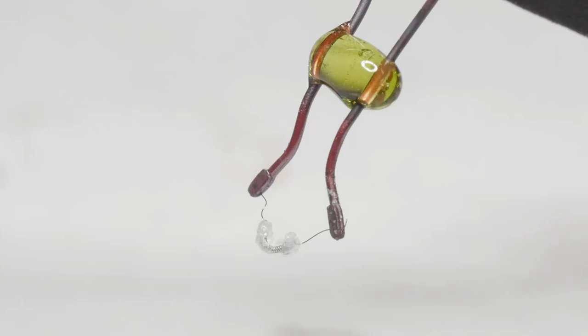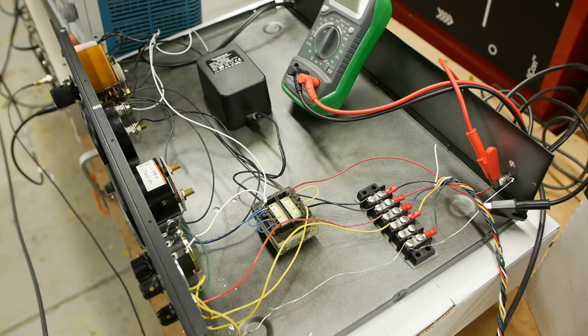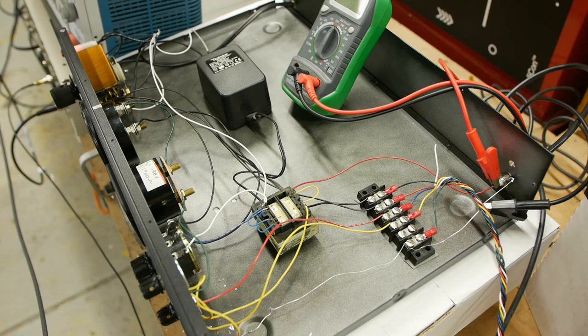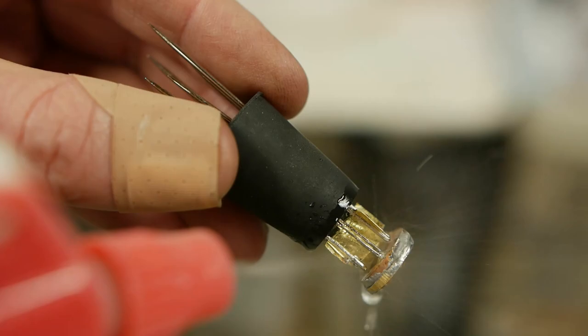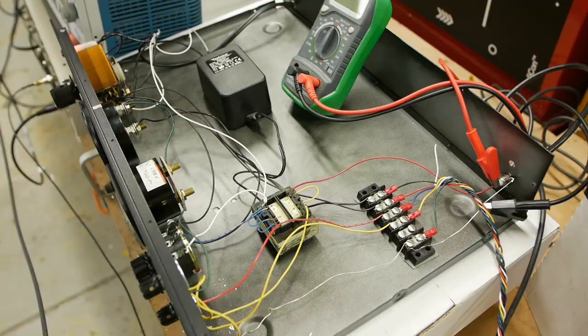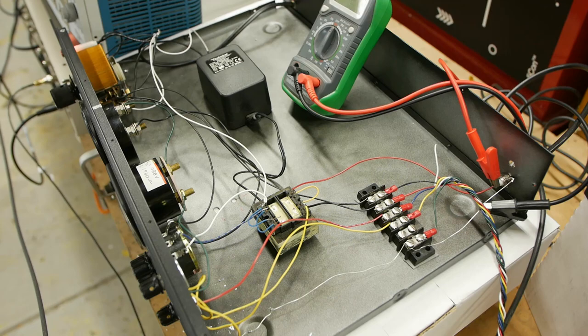Another major problem of using this thing is that the amount of mass that goes in there is limited. We put this together, putting some fluid on the tungsten filament, waiting for it to dry, then assembling the whole machine, starting it up and trying to get a signal. After the filament is hot for about 5 or 10 minutes, most of the usable mass has been boiled away. Not all of it gets ionized. A lot of it just ends up spraying the inside of that ion gun chamber. You only get 5 or 10 minutes of use out of this before it uses up all its sample. Then you have to wait for the system to cool down, bring it back up to room pressure, add more sample, put it back together, vacuum it back down, only to get another 5 or 10 minutes.